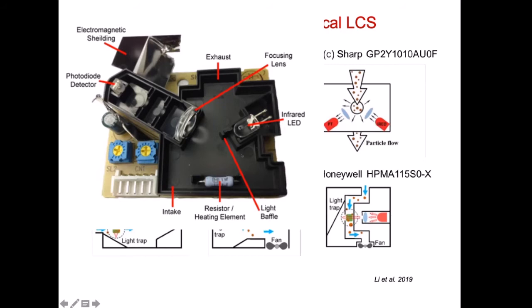So when the ambient temperature goes up, the intensity of light emitting diodes or semiconductor lasers - they're all very cheap nowadays - the stability changes. Usually when temperature goes up, the illumination power drops. When you have less light scattered on the particle, your signal is lower, meaning your recalculated mass concentration is also lower.